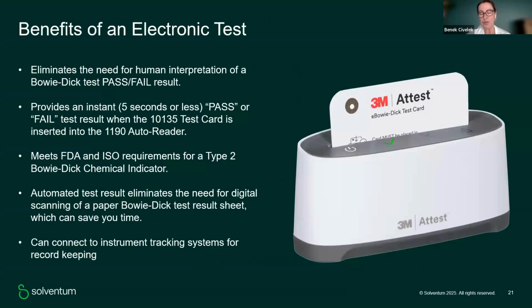So what will be the benefits? First of all, as I mentioned, the color change in the traditional pack can create errors due to human interpretation. With this design and this technology, you will have a significant result of pass or fail. When you place the card after exposure in a Bowie-Dick test cycle, you will see the result in less than 5 seconds. It fulfills all the requirements of the FDA, which has created a new subject for this kind of testing, and also the ISO requirements for a Bowie-Dick test. It is fully digital, so there is no need for interpretation and no need to keep, file or scan the test sheets, which saves time. And it can connect with the tracking systems in hospitals.